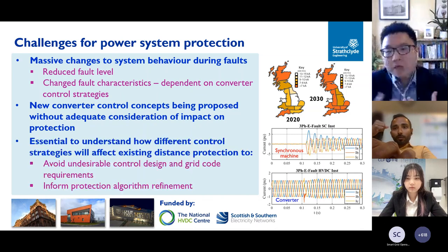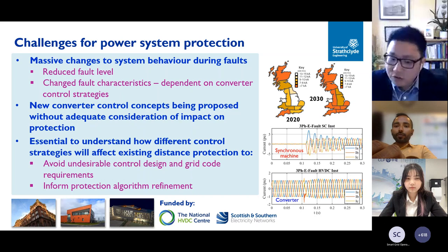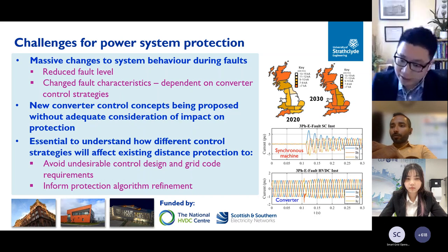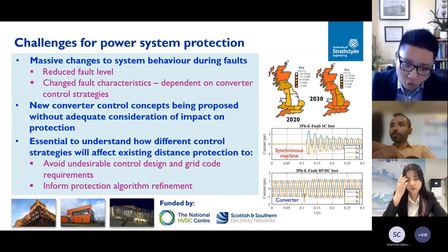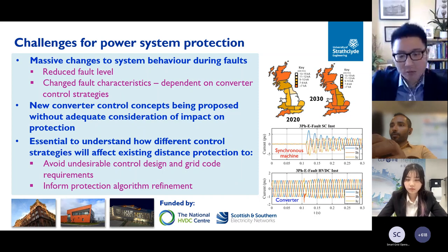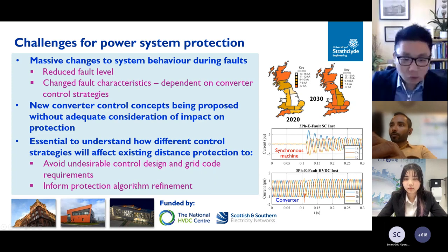Okay. Now, what we are doing with the National HVDC Center in the UK and SSEN, the utility company here, we try to understand what the challenges and root causes are, and the risk to protection operation when we have a lot more renewable generation. The purpose of doing that is to try to avoid undesirable operation.